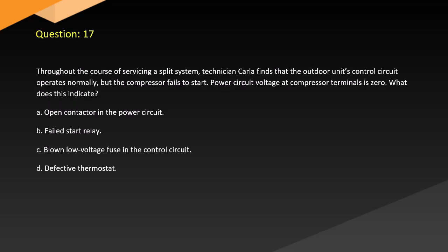Question 17. Throughout the course of servicing, split system technician Carla finds that the outdoor unit's control circuit operates normally, but the compressor fails to start. Power circuit voltage at compressor terminals is 0. What does this indicate? A. Open contactor in the power circuit. B. Failed start relay. C. Blown low voltage fuse in the control circuit. D. Defective thermostat.